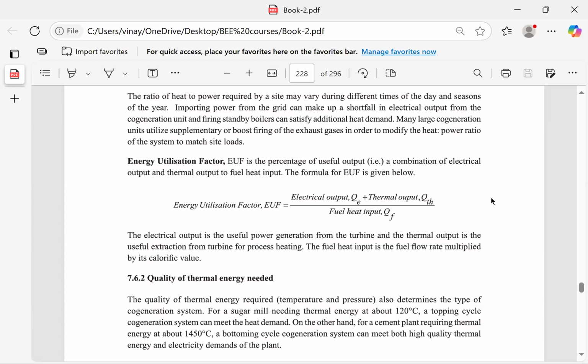Plus the process steam given to the industry contains a certain total heat per kilogram of steam—calculate how much that is. So total kilocalories equivalent to electrical generation plus process heat kilocalories, divided by the quantity of fuel multiplied by the gross calorific value per kilogram, gives a complete ratio in the same units. This ratio is called the Energy Utilization Factor.